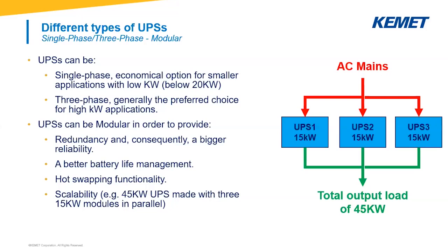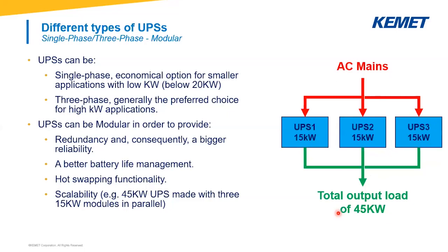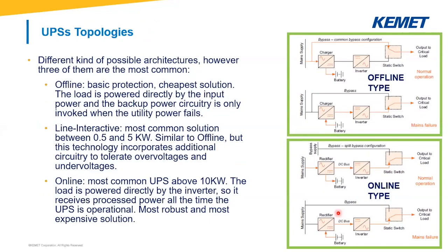And finally, another big advantage — and in my opinion this is the biggest one — is scalability. As you can see in the image on the right of the screen, we just got a 45 kilowatt UPS by putting three 15 kilowatt UPSs in parallel. An end-user can decide to improve the power of the UPS by adding another 15 kilowatt module to get 60 kilowatt, or remove one of the modules if the power need is decreasing.